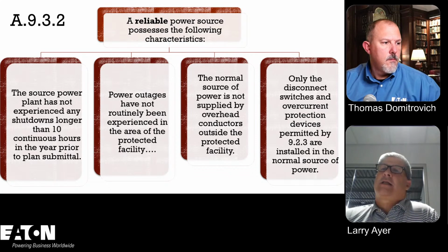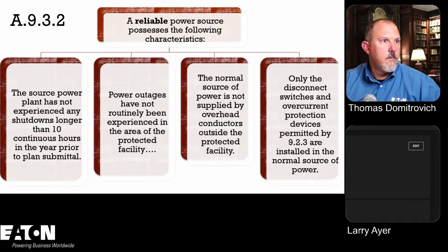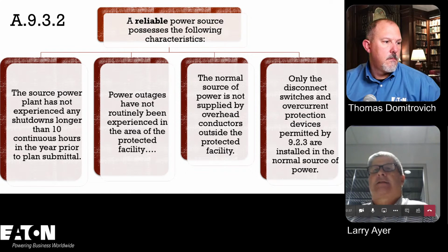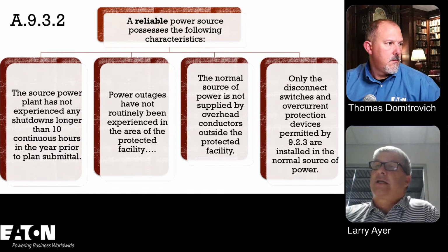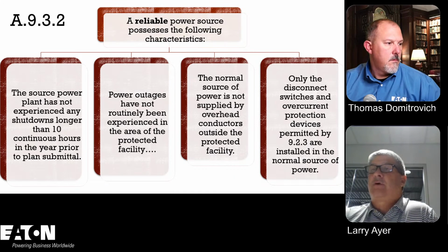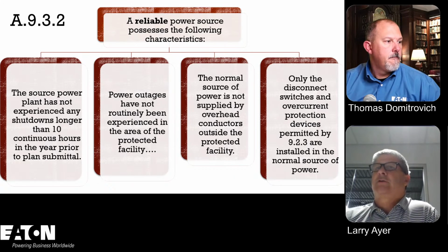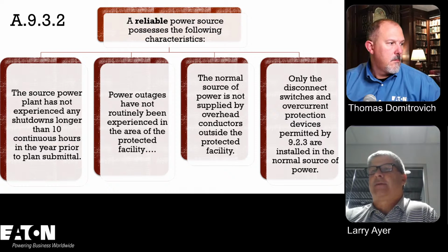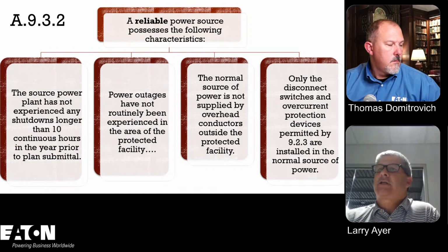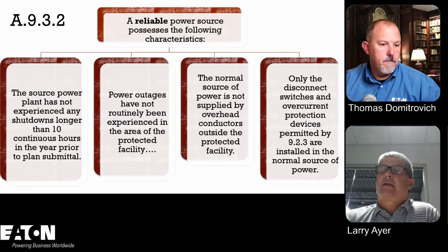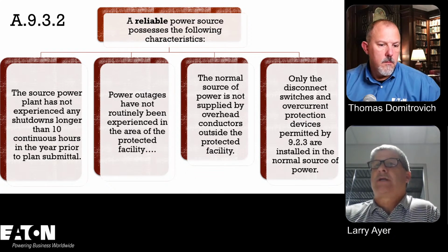A lot of times when I've designed things in downtown Cincinnati, for example, I'm looking at a downtown that has two substations feeding it. It's a 208 volt network. Maybe power's gone down once every 20 years. Inspectors and plan review officials look at those things and say, if you're fed from the 208 volt, I consider that reliable. Some of those things are determined by the AHJ, and they have their own method of determining whether something's reliable or not. But in the annex here, they give you some suggestions on what they say is reliable.